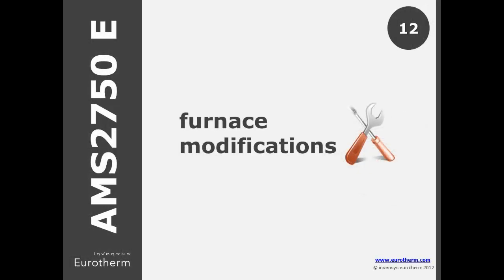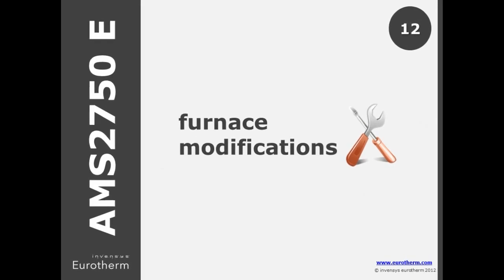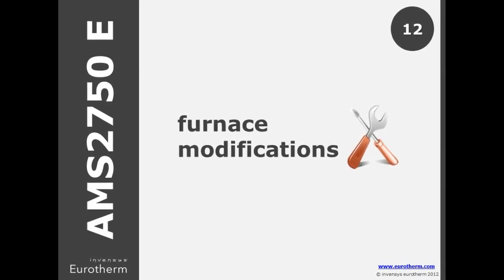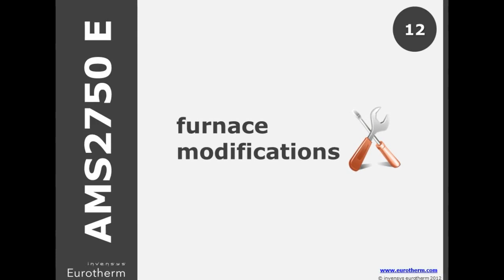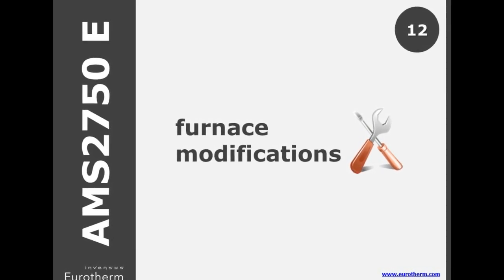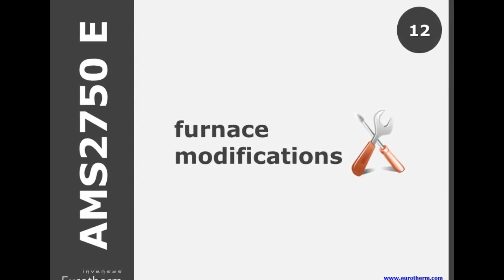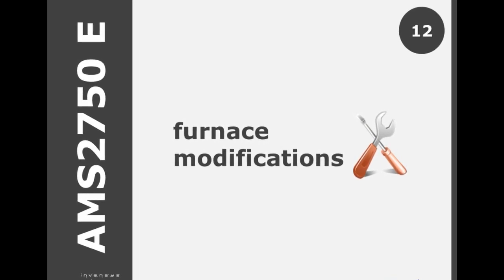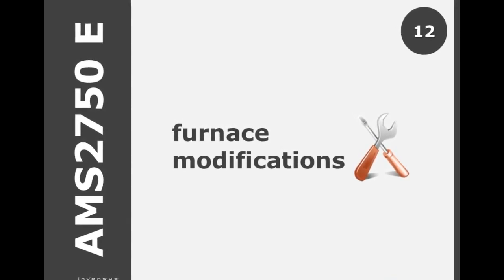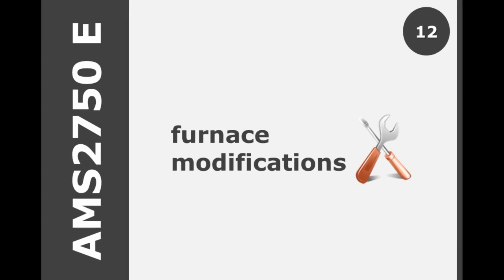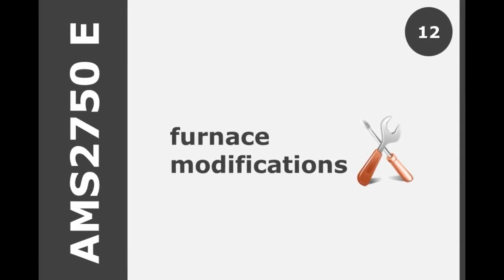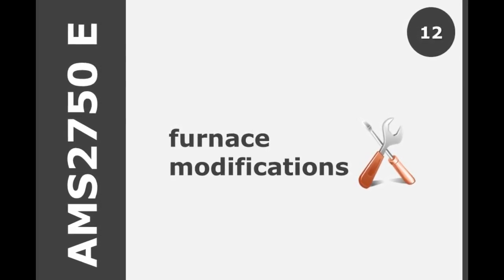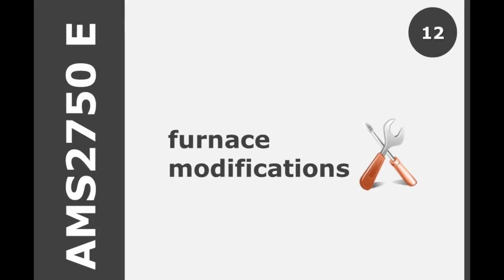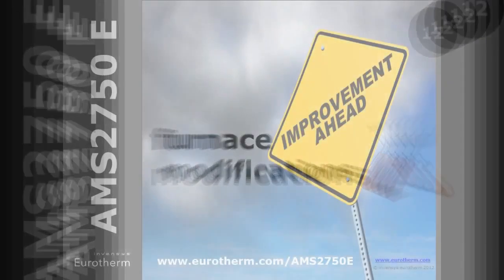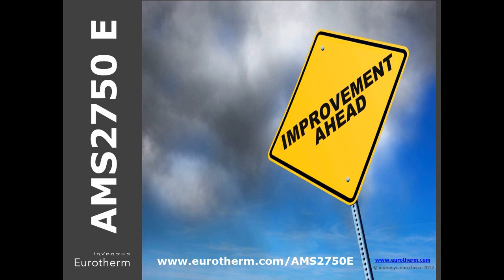Major furnace modifications require resetting back to an initial survey frequency. Indeed, this included changes of control type, for example, proportional versus high-low, off-on, and adjustment of tuning constants. In E, further detail was added to include change of controller model or type, PLC logic program change to the furnace heat control, adjustment of tuning parameters. I hope this was a useful summary of 12 key changes between the D and E revisions.